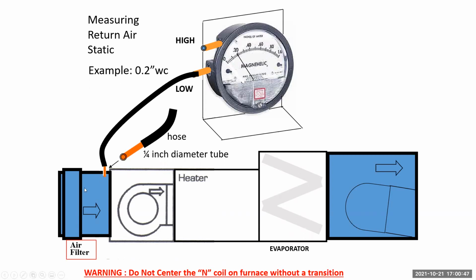But here, looking at return, you'll see where your air filter is. It's right above that box that says air filter. So we're between the filter and the blower is where we want to go. You'll see they have their tube just barely stuck right inside that ductwork. That's all it takes. No more than 1/8 of an inch through the side of the duct. Do not go more than that, or your numbers will be completely off-centered. Pay attention down here. We're going to talk about this here in a minute. Do not center an N coil on furnace without a transition. We'll talk about that here in a second.